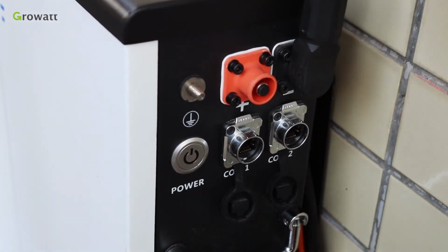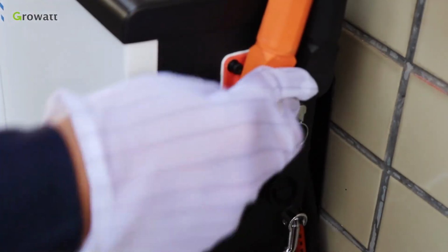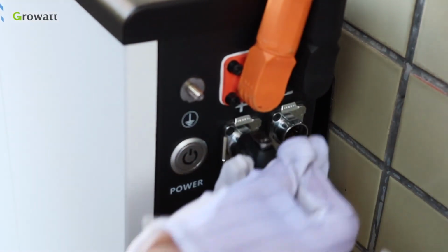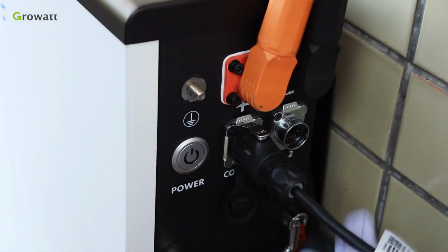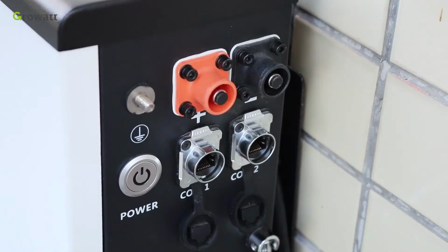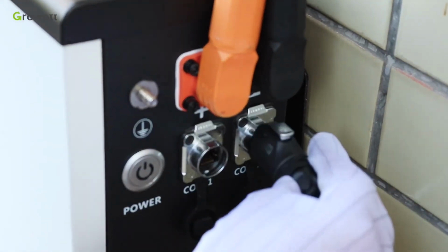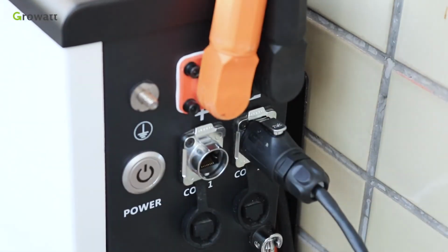the ground terminal, the battery positive power terminal, and the battery negative power terminal. For connection, firstly connect the positive and negative power cable from the inverter to the battery. Connect communication cable from inverter to COM.1 port. Secondly, connect the power and communication cable from the first battery to the second battery.